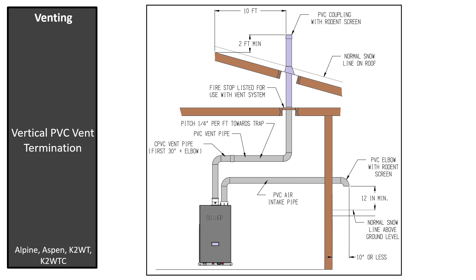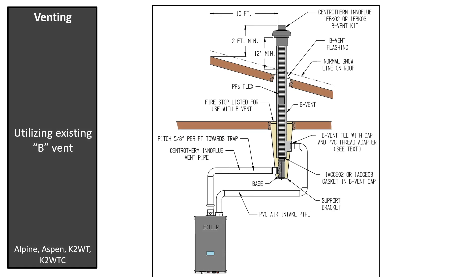As another option of vertical venting, we can run a single pipe through the roof and the intake through the sidewall. When any type of vertical venting is applied, the vent termination must be two feet higher than anything within 10 feet horizontally. Using an existing B vent for venting and air intake, use a polypropylene flexible pipe and kit numbers referenced in the charts in the I&O manual to complete the installation.